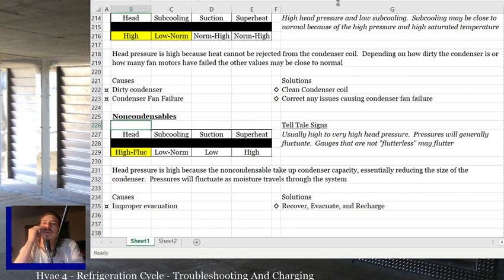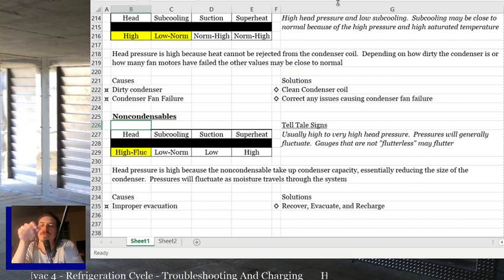Non-condensables, you will have a high head pressure. A lot of times it's a very high one, but it may be fluctuating between normal and high, but you will have a high head pressure. And the trick here is the fluctuation, because usually you'll see a fluctuation. Telltale sign is usually high to very high head pressure. Pressures will generally fluctuate. Gauges that are not flutterless may flutter.